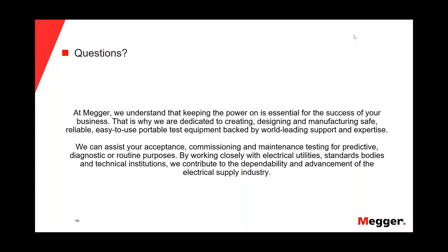The 1,000 pC here that's mentioned, this number was given for splices, and you have to be a little careful about using numbers when you talk about PD levels, acceptable PD levels, because it depends what the splice or the termination is made from. If you have solid dielectric, they have typically lower acceptable levels than fluid filled termination or splices. But like I say, the 1,000 in the field is a number that when you measure it, you need to do something about it. It's a warning flag, where the 5 pC is what it should be when it leaves a factory.